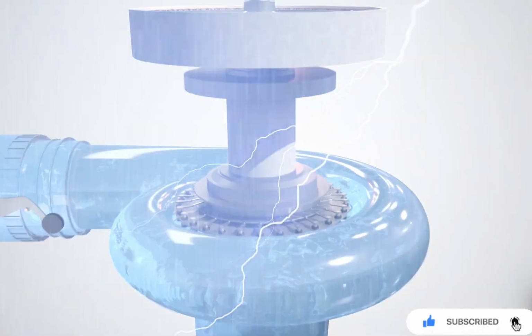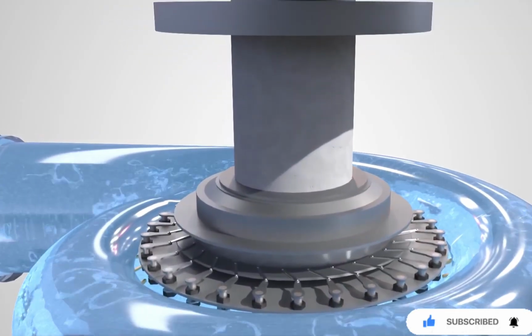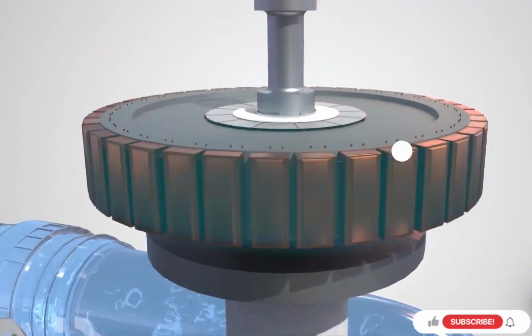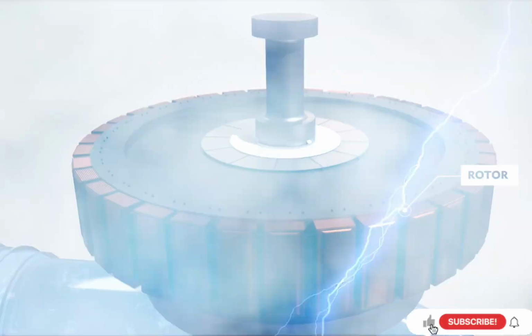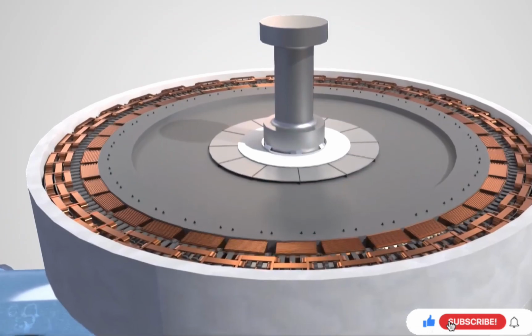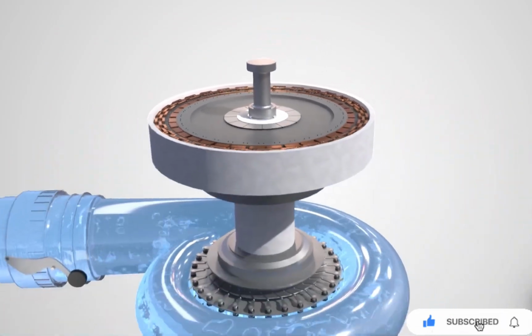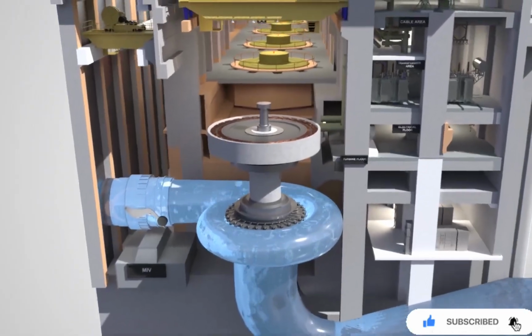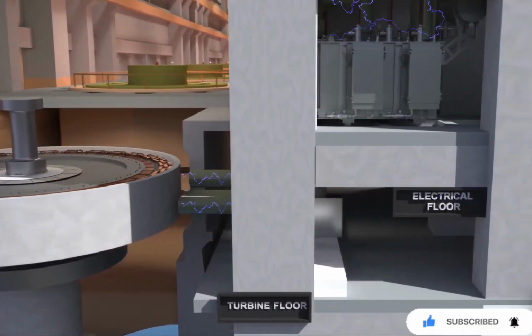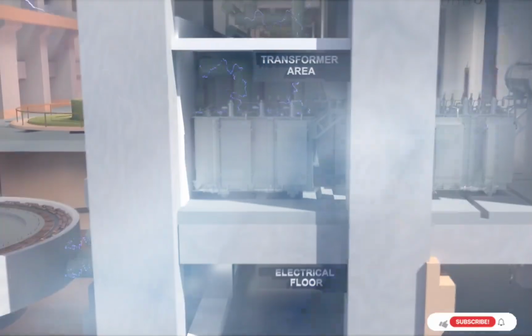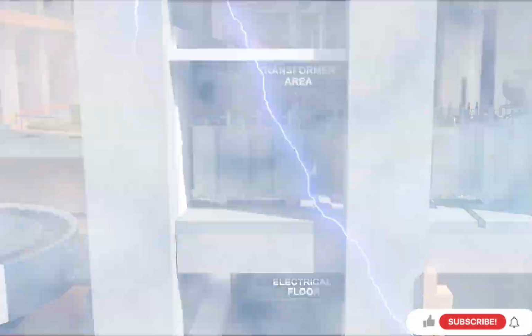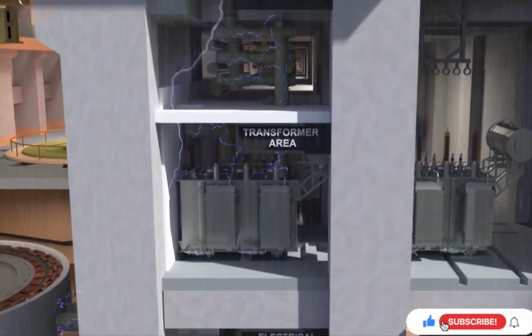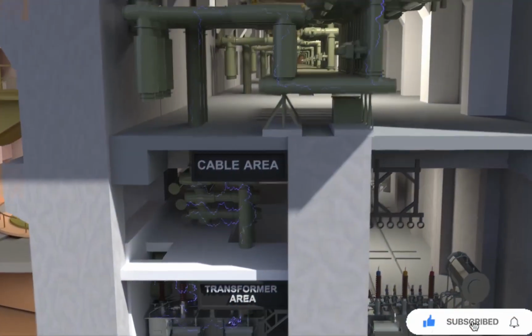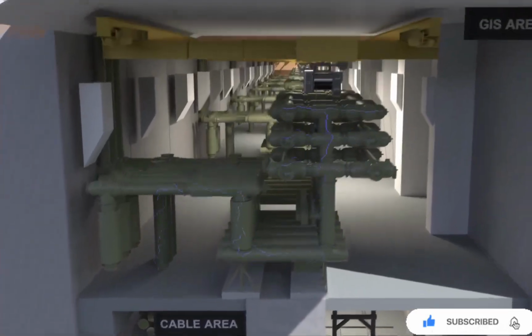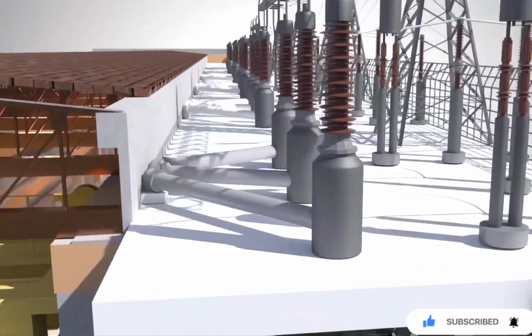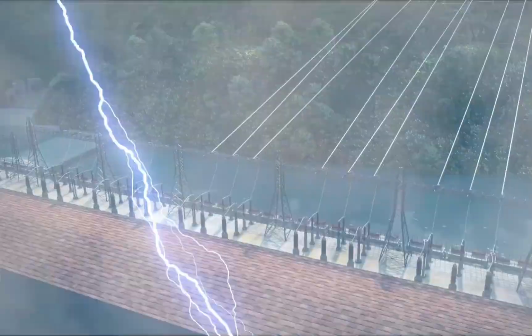Rotating turbine shaft is coupled to the shaft of the generator rotor, the biggest rotor ever handled in a hydropower plant weighing 620 ton. This generator rotor creates a rotating magnetic field, which in turn helps in generating electricity through generator's stator windings. The generator transformers step up the generating voltage from 16 kV to 400 kV. GIS is used as switching system to connect the generating units with pothead yard and 400 kV transmission lines.